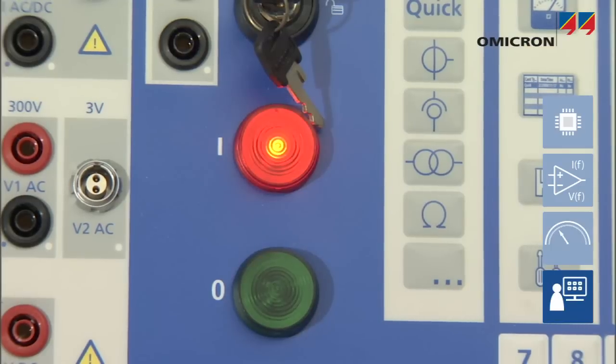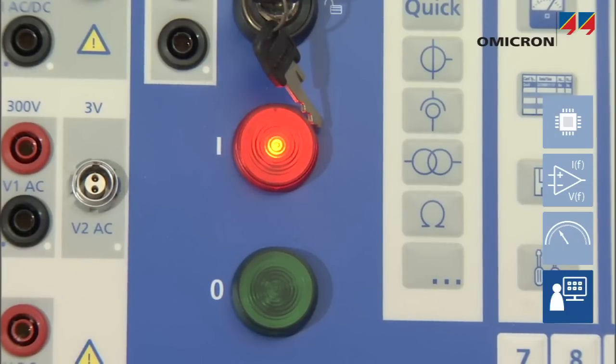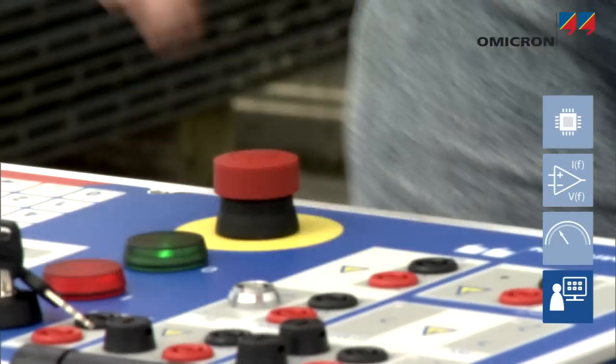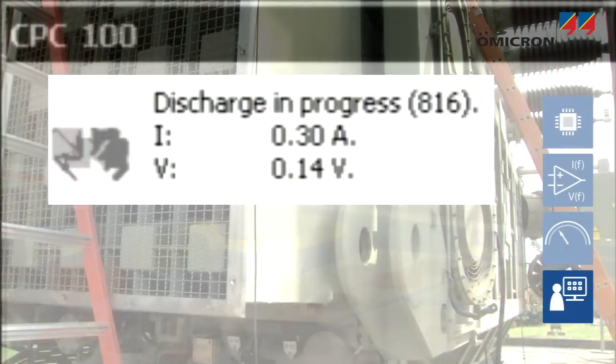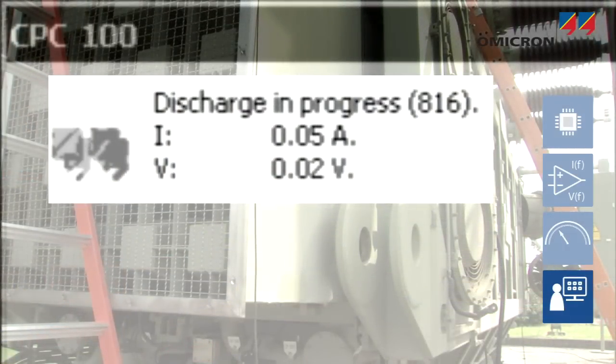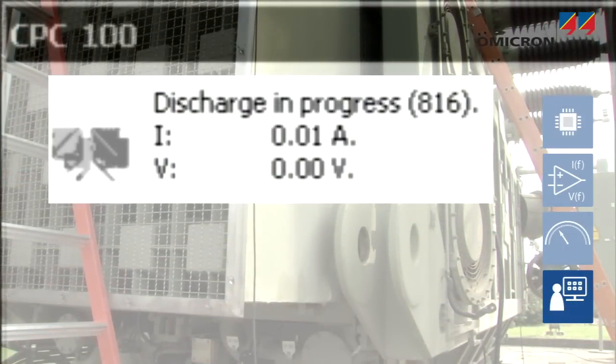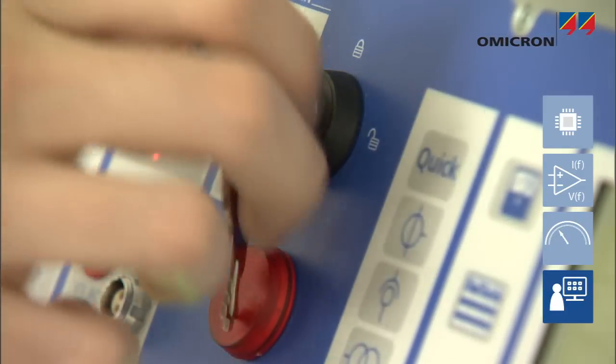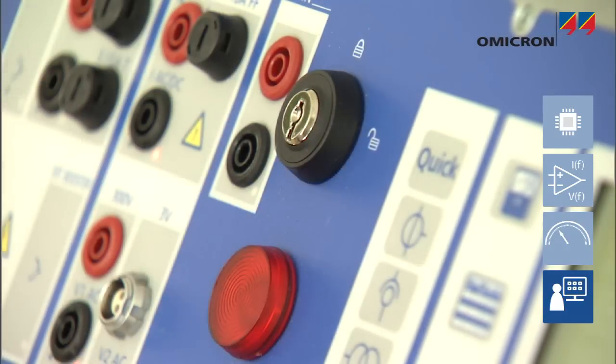Flashing lights on the front panel clearly indicate the injection of voltage or current. An emergency off button immediately stops all injection and discharges the energy stored in the test object, such as a transformer winding. The CPC can also be locked to prevent unintended activation.